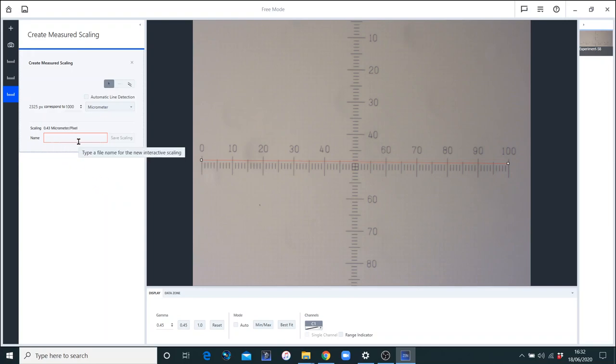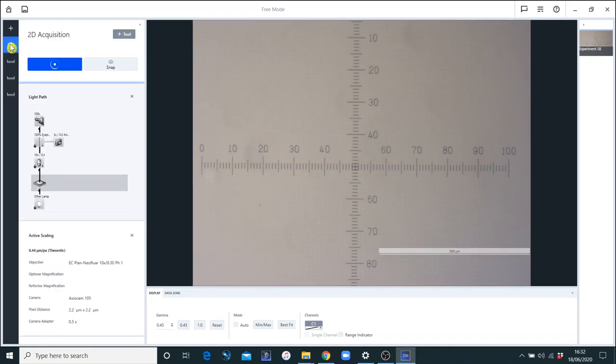Now the trick here is to make sure we save the scaling by the same name as the objective, which in this case is 10x. So enter the name and save scaling. Now, it will save it, although it doesn't tell you it saved it. So just be aware that once you click on save scaling, you have saved it.